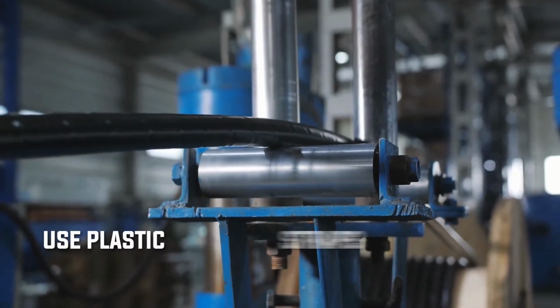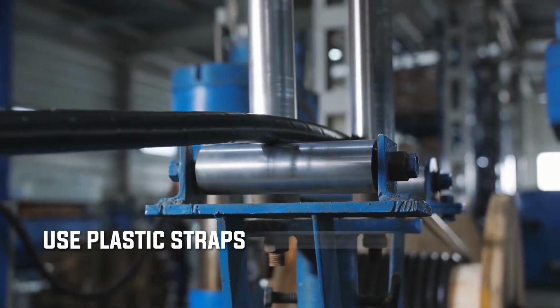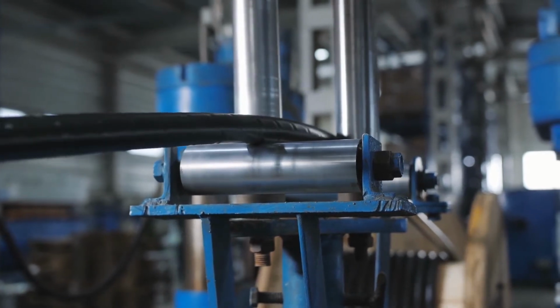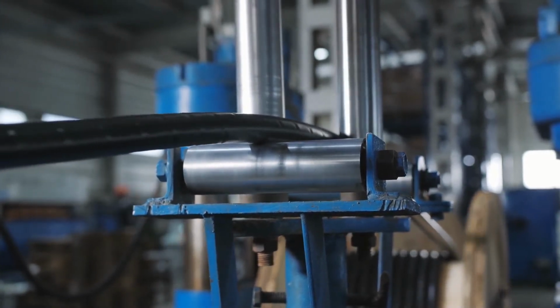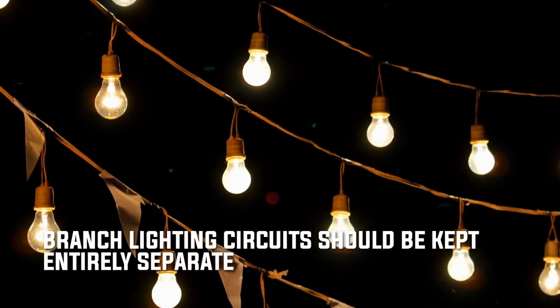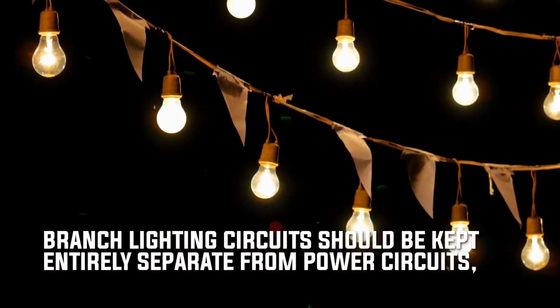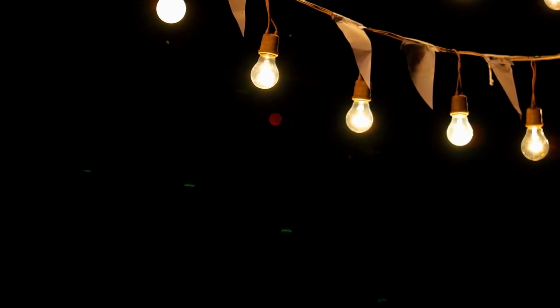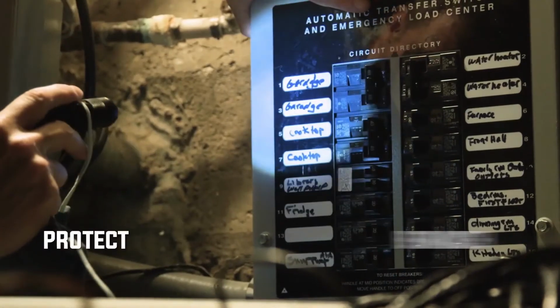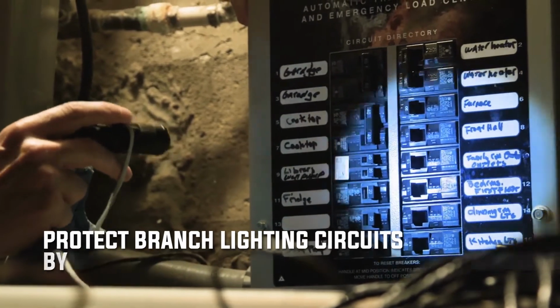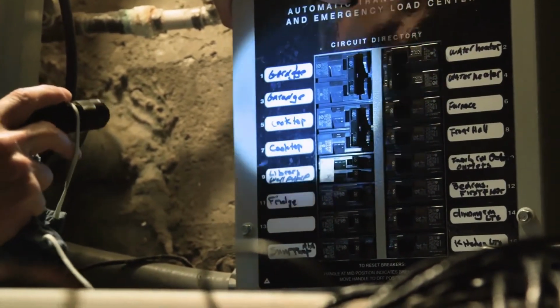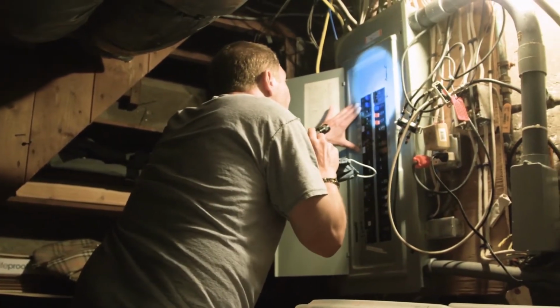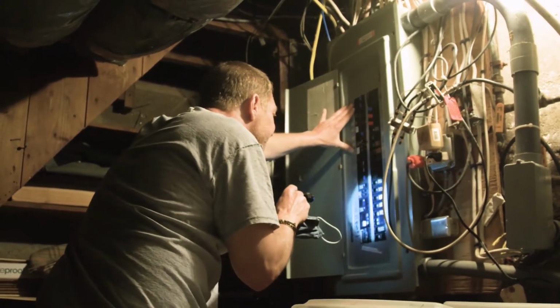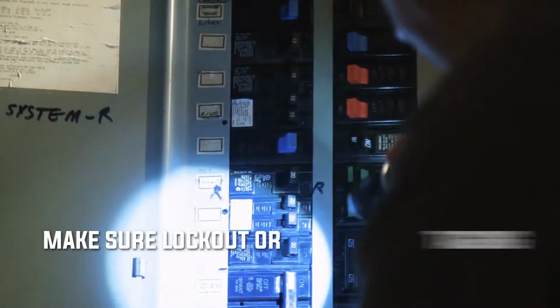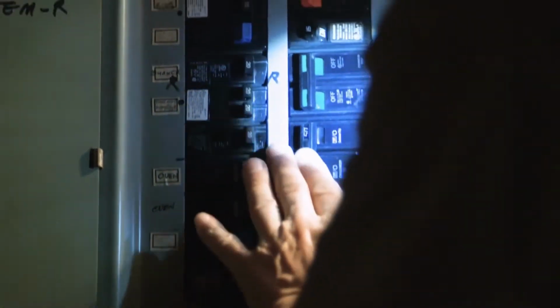Use plastic straps or insulated wiring instead of metal nails, bare wire, etc. to secure the lights. Branch lighting circuits feeding temporary lighting should be kept entirely separate from power circuits except for a common supply. Protect branch lighting circuits by a breaker or fuse with a 15 amperes rating. An electrician should connect the circuits directly into a distribution panel. Make sure lockout or tagging procedures are followed before connecting the wire to the panel.